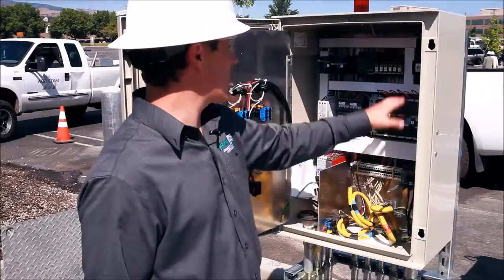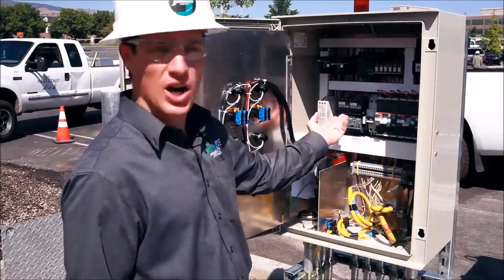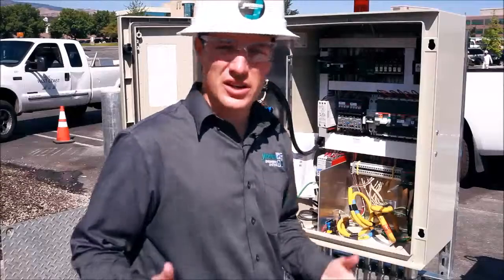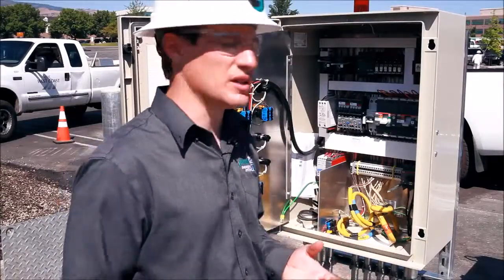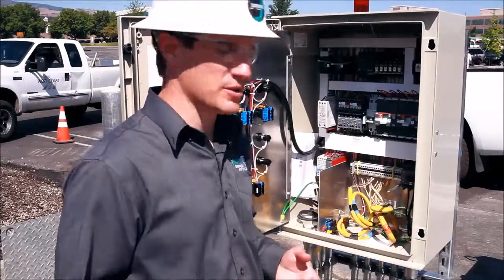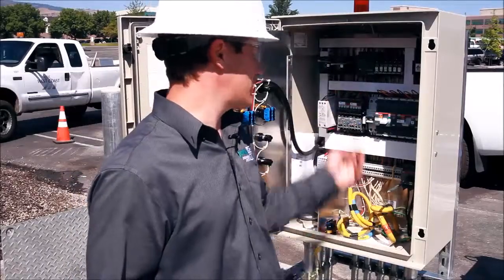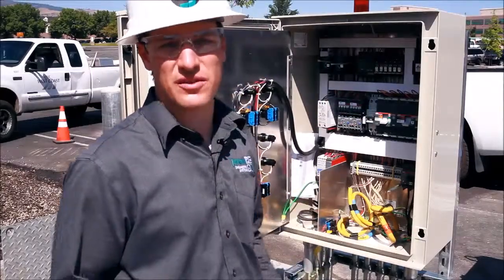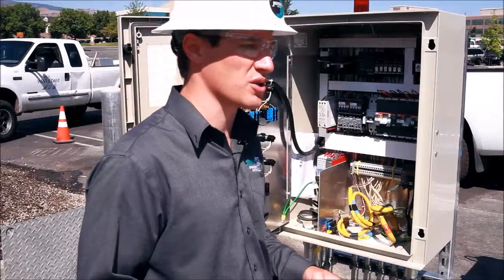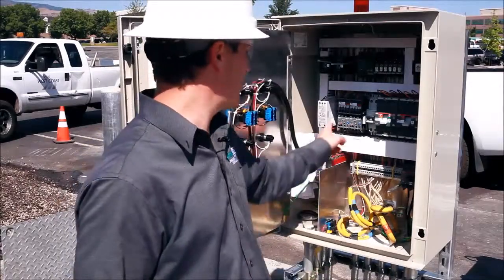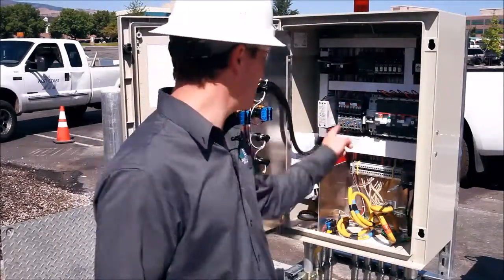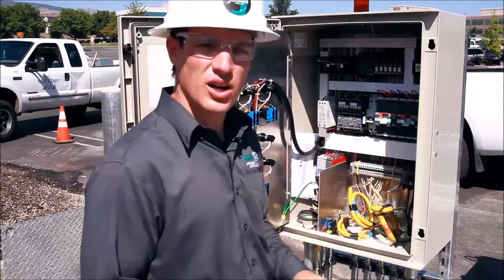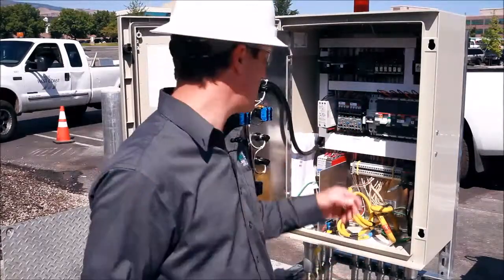From the breaker, then the power flows to the motor contactors. The motor contactors are essentially the hands of the PLC. This is how the computer turns the pumps on and off. So when the PLC reads an input from the level detection device, in this case a pressure transducer, to turn the pumps on, it generates the output and it lets the contactor suck in. So you'll actually see that white motor contactor depress in. You can hear the sound as well.